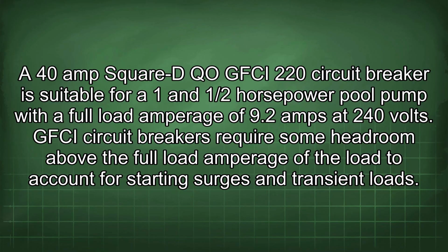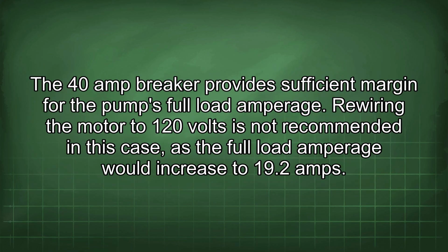A 40 amp Square-D QO GFCI 220 circuit breaker is suitable for a 1 and 1/2 horsepower pool pump with a full load amperage of 9.2 amps at 240 volts. GFCI circuit breakers require some headroom above the full load amperage of the load to account for starting surges and transient loads. The 40 amp breaker provides sufficient margin for the pump's full load amperage.